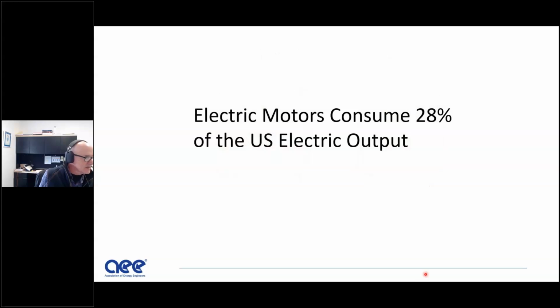So motors consume 28% of the US electric output, so it's a pretty big deal. If we can find ways to save energy on motors, it would have a big impact on not only decarbonization, but also reducing emissions and saving a lot of money. And that's what we're going to talk about. 28% would be greater than 1 trillion kilowatt hours a year. Imagine saving 50% of that with VFDs.